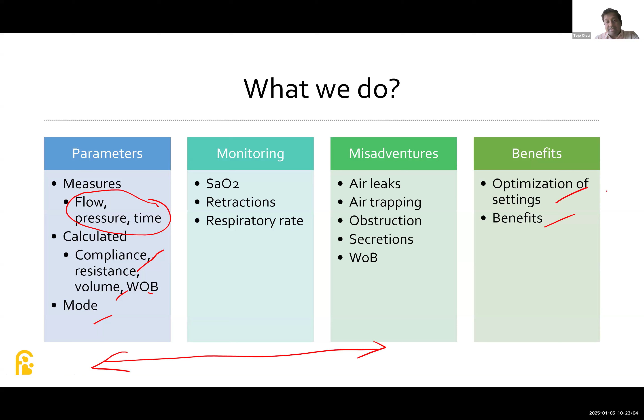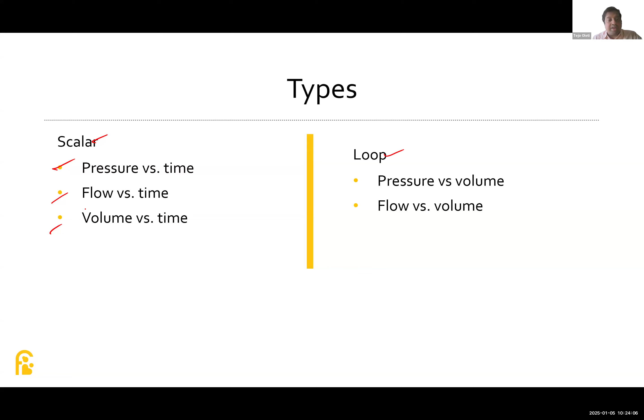The scalar graphic means they are plotted against the time. So different parameters, pressure, flow, volume, are plotted against the time. That means that in a breath cycle, while it is going on from 0 to the next second, how these three changes are happening. And the loop will look at the parallel changes that are happening between the pressure and volume, and also flow versus volume. Pressure versus flow also some people use, but in neonatology we currently use only these two techniques. So scalar graphics are plotted against the time. For understanding's sake, in the next few slides, we will demonstrate how any mechanical breath will look like.